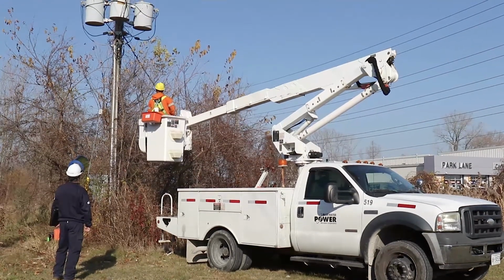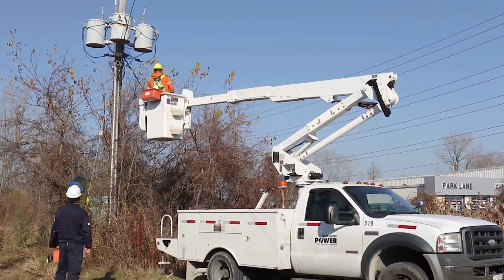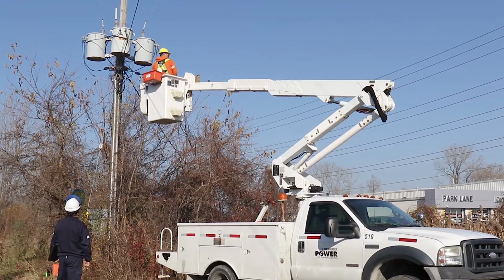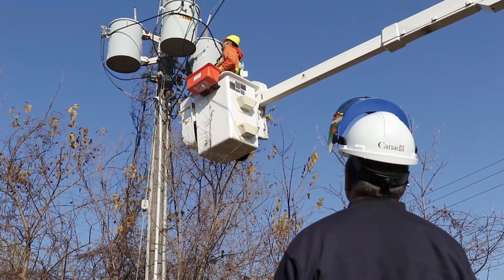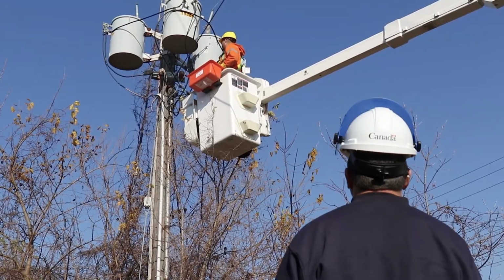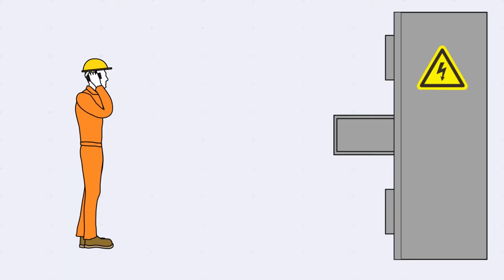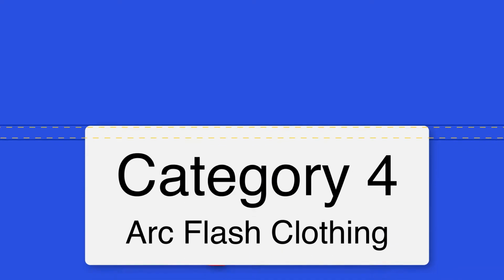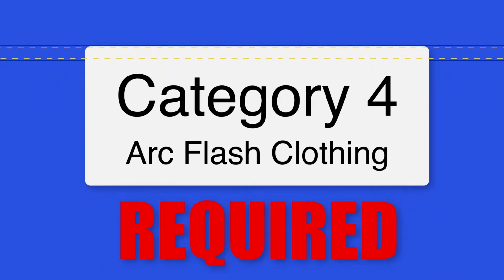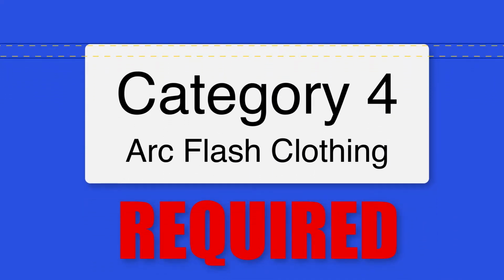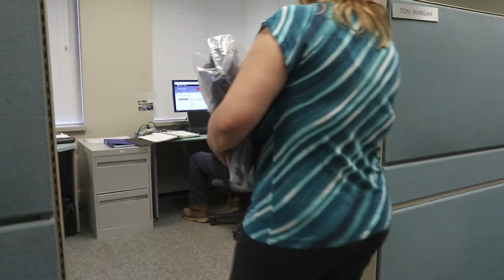Measurement Canada inspectors are not permitted to conduct inspections on high-voltage type metering services. You should know how to recognize and identify these types of installations in order to call in the electrical line crew. In some cases, the utility may require Category 4 arc flash clothing regardless of Measurement Canada standards. And if that is the case, the Measurement Canada inspector must seek an alternate means of conducting the installation inspection, confirming the necessary end result while ensuring his personal safety.